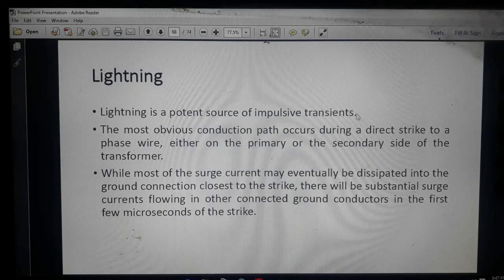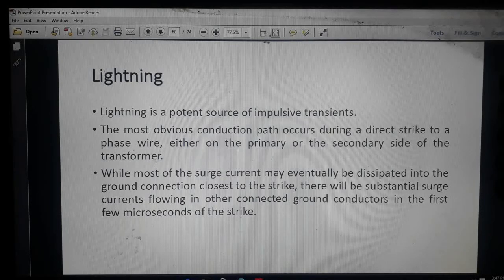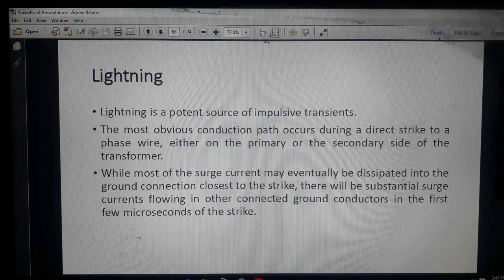Impulsive transient will be generated if the most obvious conduction path occurs during a direct strike to the phase wire, either on the primary or secondary side of the transformer. If lightning is generated above or near our transmission system, it may be directed straight to the phase wire, either on the primary side or secondary side of the transformer, and an over voltage transient may be generated. While most surge current may eventually be dissipated into the ground connection closest to the strike, there will be substantial surge current flowing in other connected ground conductors in the first few microseconds of a strike.